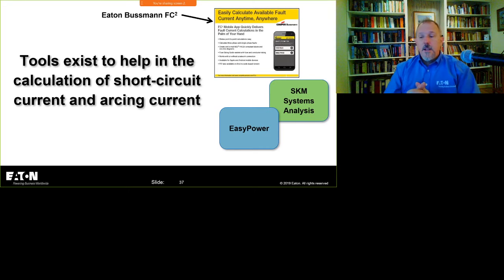And in fact, even if you're using infinite bus, there is an IEEE paper, which I will put in the links down below to this YouTube video. We have an IEEE paper that our Eaton Engineering Services Division wrote, which helps us understand that if a utility gives you a 3-phase bolted fault that's based on infinite bus, you can cut that in half and use that for your arcing current calculations.